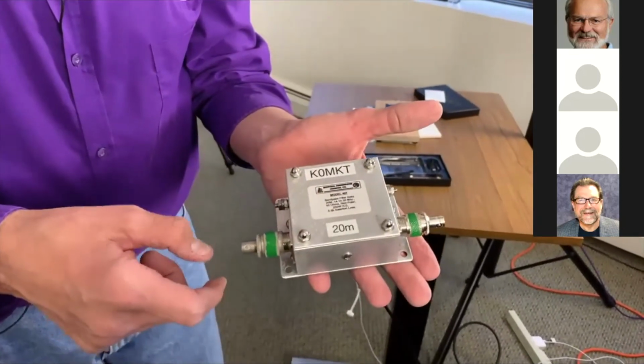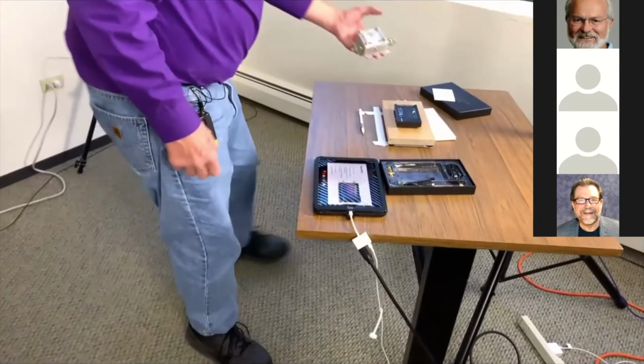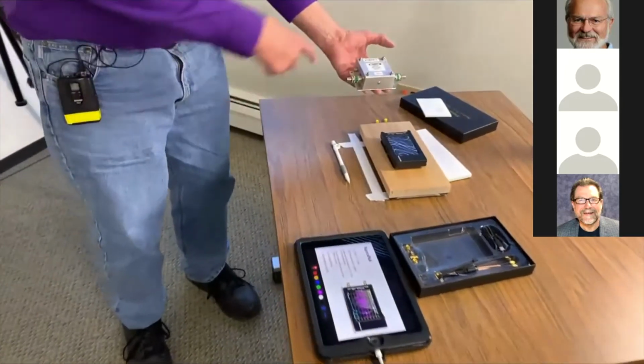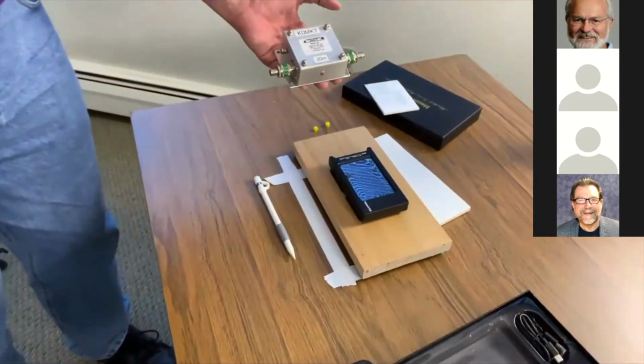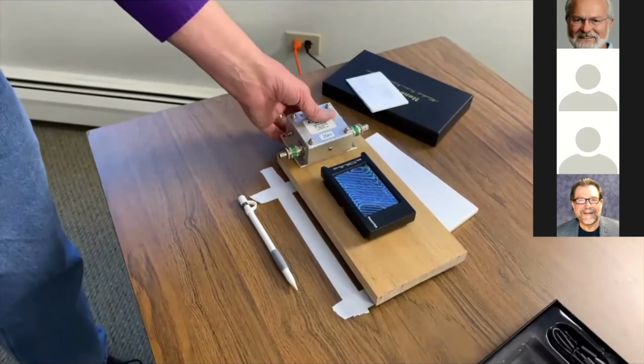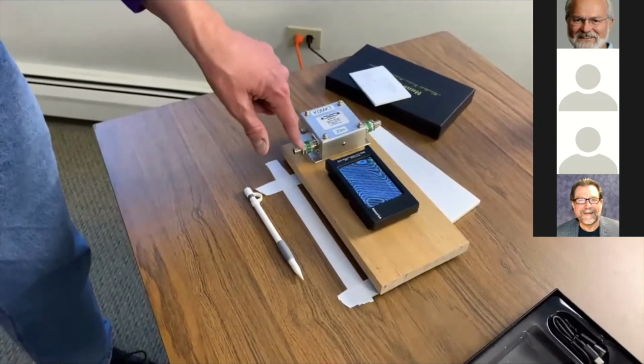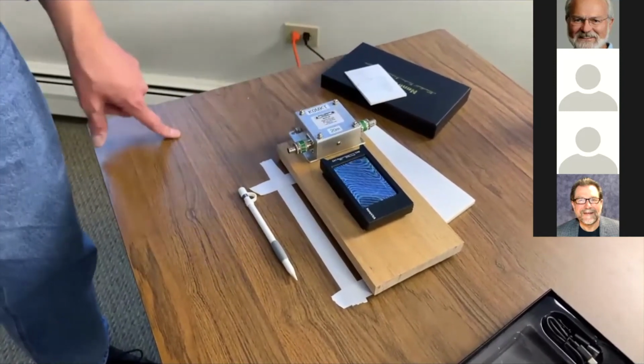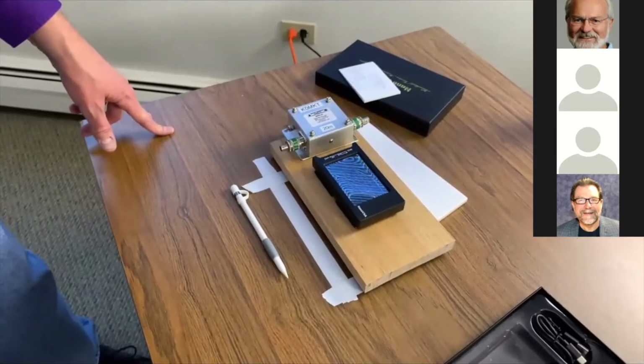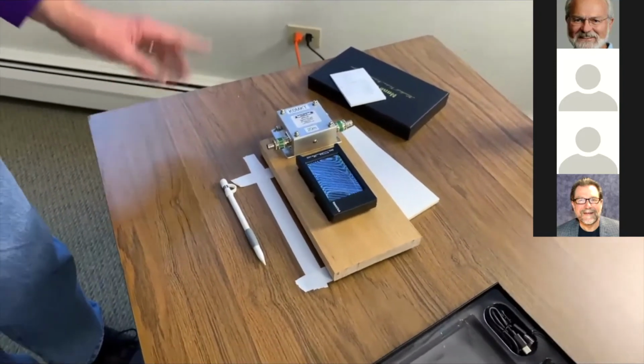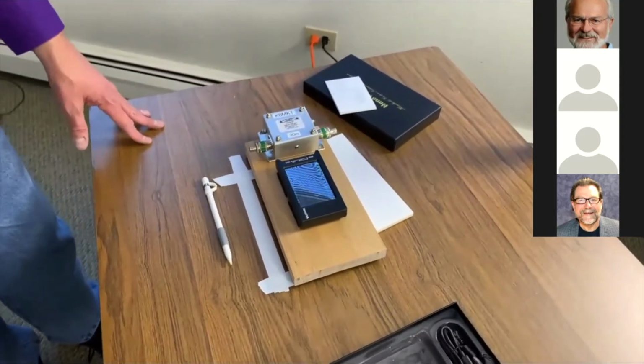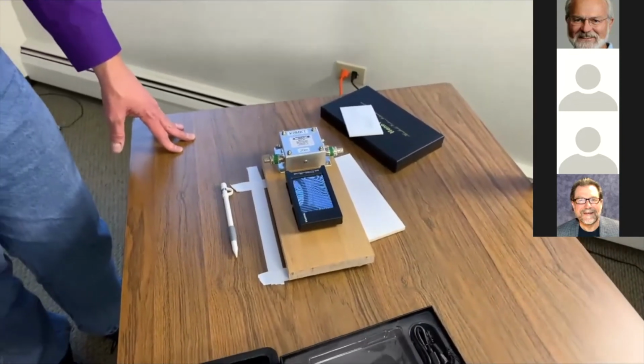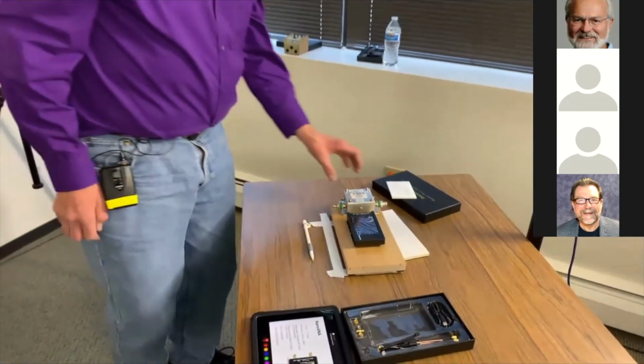If you were to connect it to the vector network analyzer, you could characterize the frequency response of this, and look at mismatch in the cable between them. That's something you would do mostly when you're designing. Day to day, we have other ways to look at that, and we'll take a look when we get to spectrum analyzers here in a second. We'll put this on the spectrum analyzer and have a look.